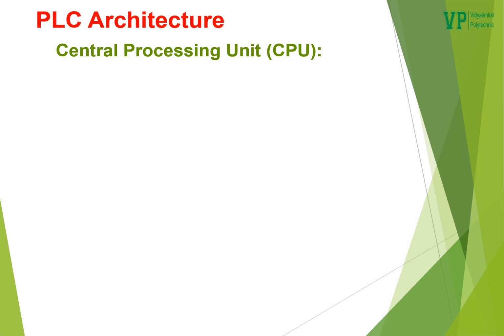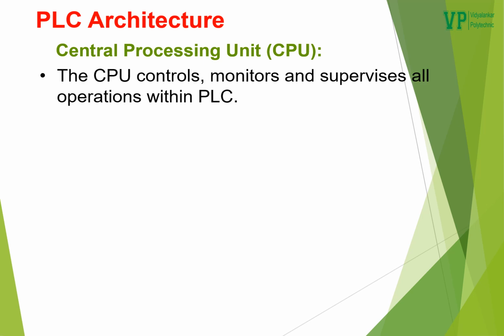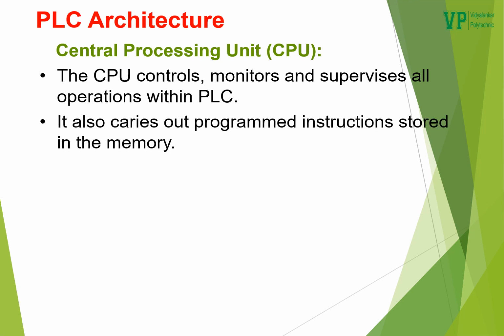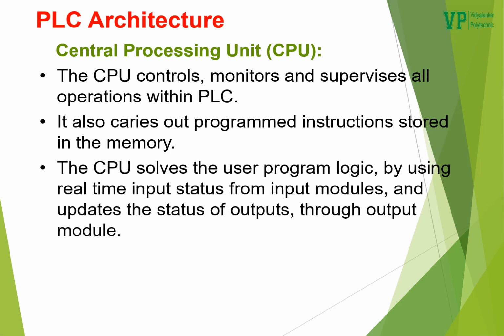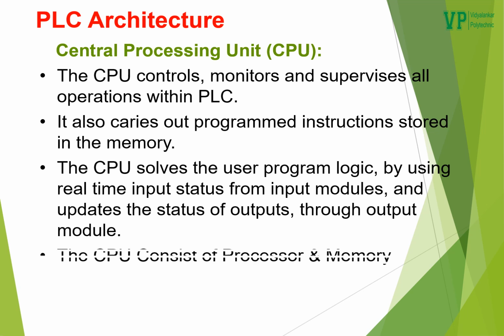Now let's study all the components one by one. We begin with the central processing unit. The CPU controls, monitors, and supervises all the operations within the PLC. It also carries out programmed instructions stored in the memory. The CPU solves the user program logic by using real-time input status from the input modules and updates the status of output through the output module. The CPU consists of a processor and memory.